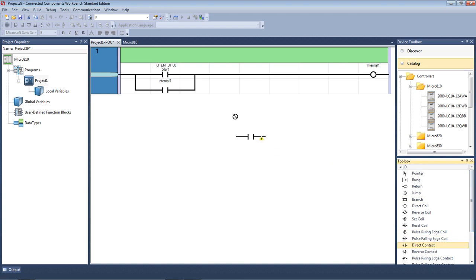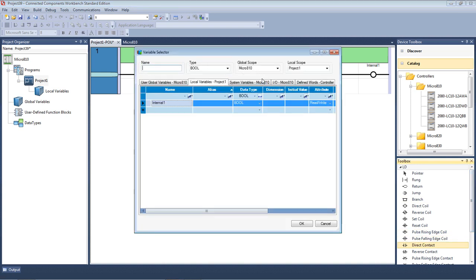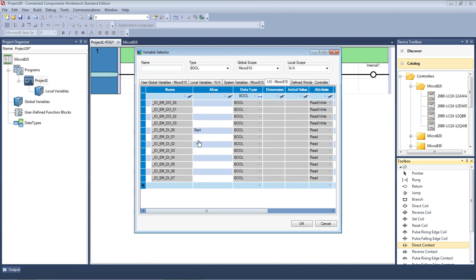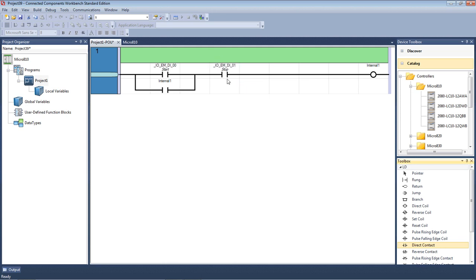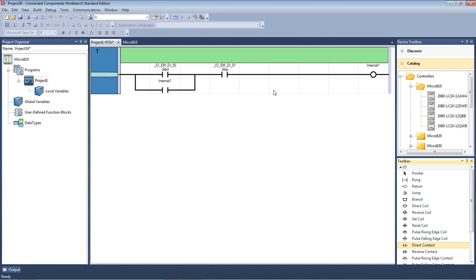Let's put another contact, let's put a stop button in as well, so that'll have to be an actual input, so for a stop. You'll also notice for my stop button here, I'm using a normally open contact, I don't use normally closed like I do with my normal circuit diagram. The reason is the actual stop button in the field takes care of that stop function, and that feeds a closed function to the logic. So when we switch this on, our normally closed stop button in the field will signal to this to actually close. So all our logic, same with overloads and so forth, will show us with a normally open. So that's the difference between our relay logic and the logic we apply to our circuit diagrams.